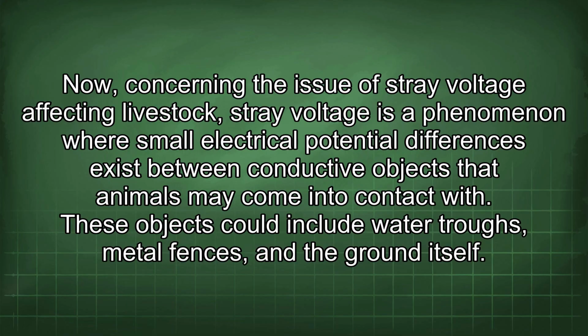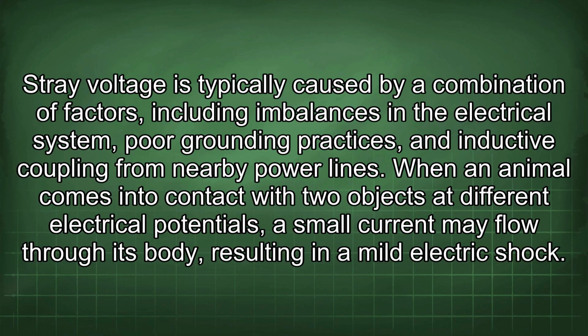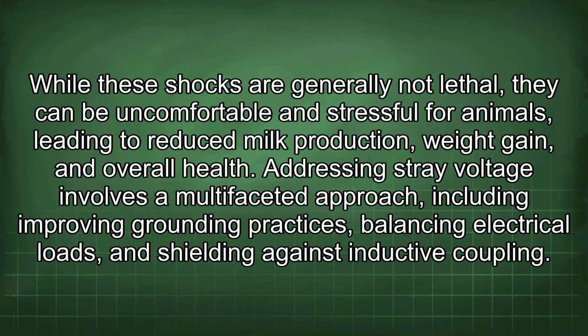Stray voltage is a phenomenon where small electrical potential differences exist between conductive objects that animals may come into contact with. These objects could include water troughs, metal fences, and the ground itself. Stray voltage is typically caused by a combination of factors, including imbalances in the electrical system, poor grounding practices, and inductive coupling from nearby power lines. When an animal comes into contact with two objects at different electrical potentials, a small current may flow through its body, resulting in a mild electric shock. While these shocks are generally not lethal, they can be uncomfortable and stressful for animals, leading to reduced milk production, weight gain, and overall health.